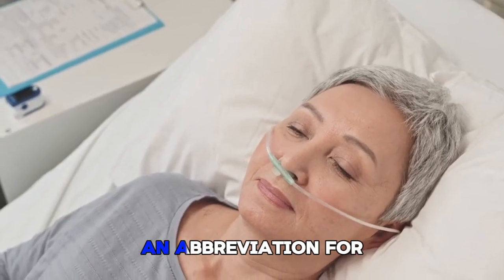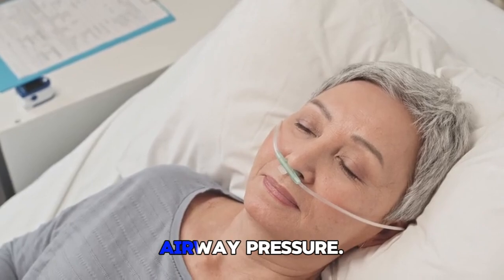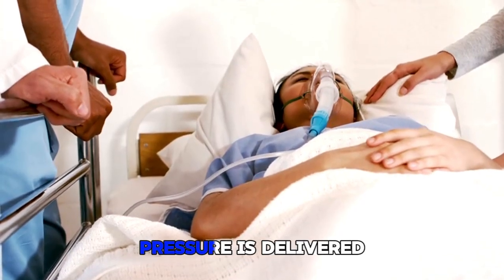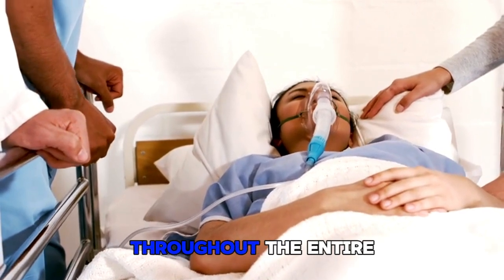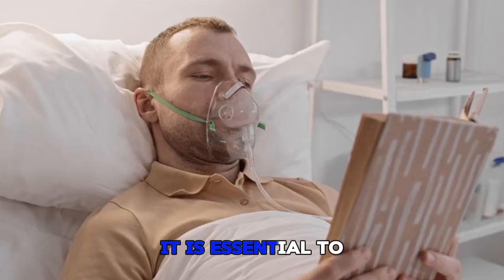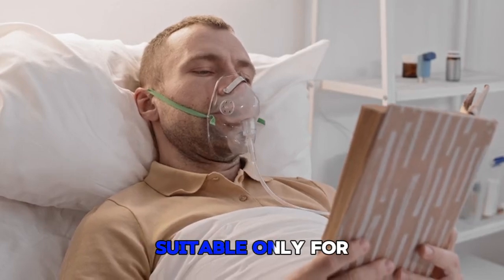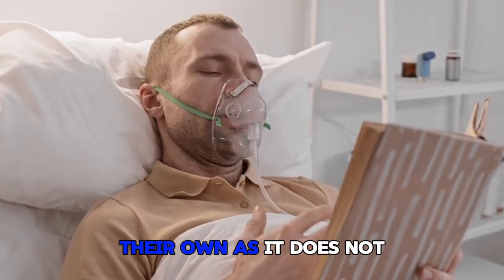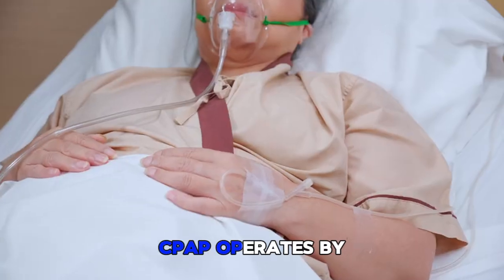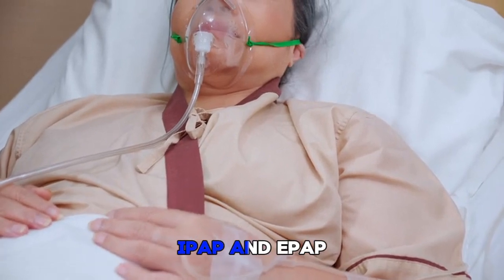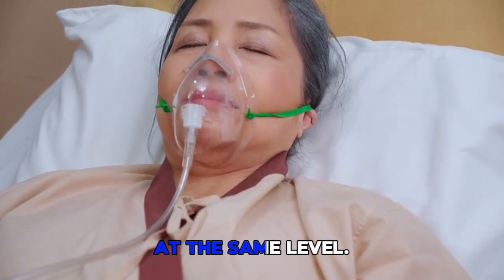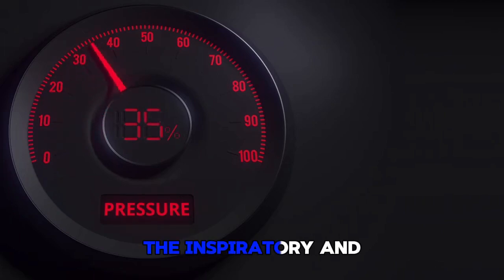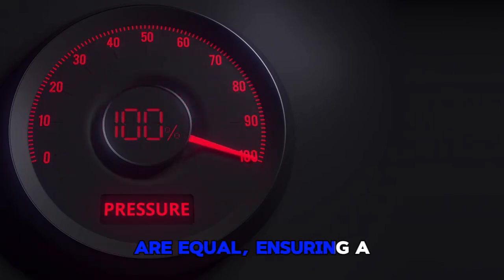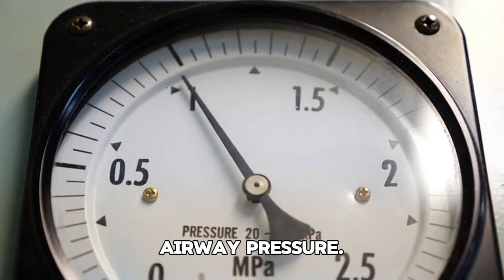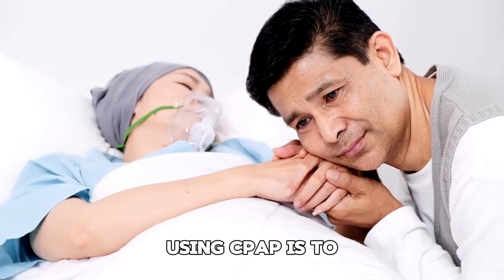Let's delve into CPAP, an abbreviation for continuous positive airway pressure. With CPAP, positive pressure is delivered continuously throughout the entire breathing cycle. It is essential to mention that CPAP is suitable only for patients breathing on their own, as it does not involve any mechanical breaths. CPAP operates by ensuring that the IPAP and EPAP pressures are set at the same level. This signifies that the inspiratory and expiratory pressures are equal, ensuring a constant positive airway pressure. The main reason for using CPAP is to treat obstructive sleep apnea, OSA.